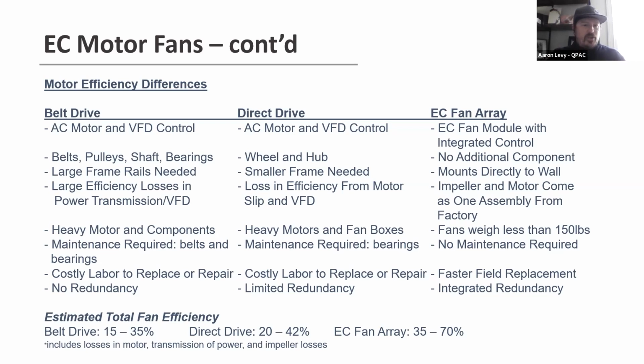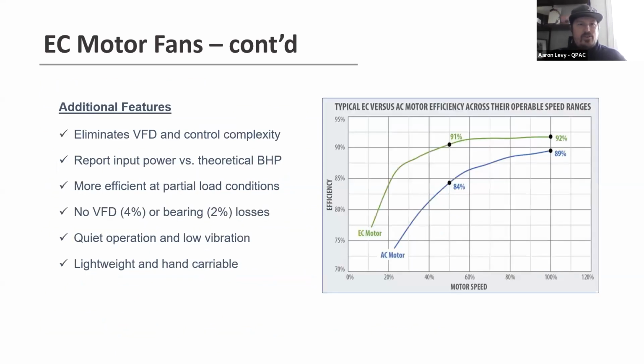And we normally talk about total fan efficiency for systems versus motor efficiency. So belt drives at best are probably anywhere from 15 to 35% of total fan efficiency. Direct drives 20 to 42, and then EC fans can be anywhere from 35 to 70%, depending where it operates on the curve. So that payback for that customer is a lot faster in the grand scheme of it. And then when we talk about motor efficiency, those motors like Baldor Marathons, those Super E's and things like that, they tend to be anywhere from 88 to 92% at full load.